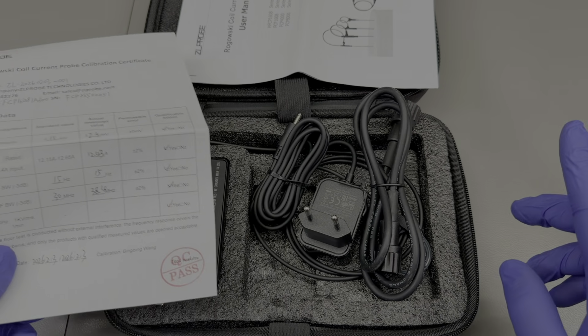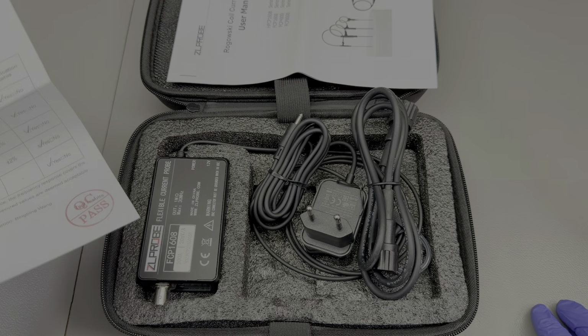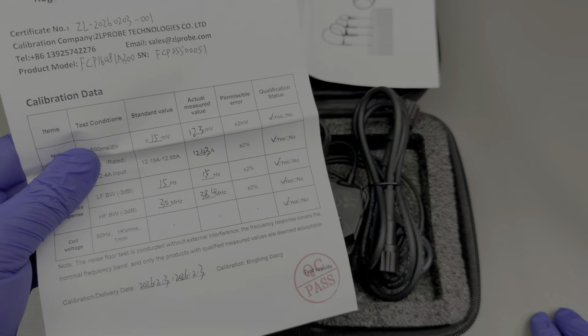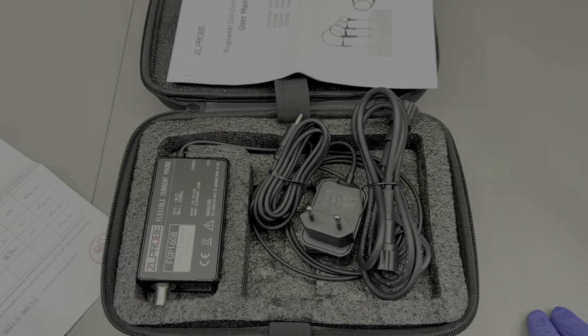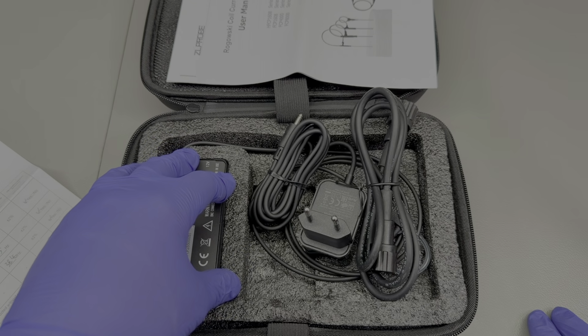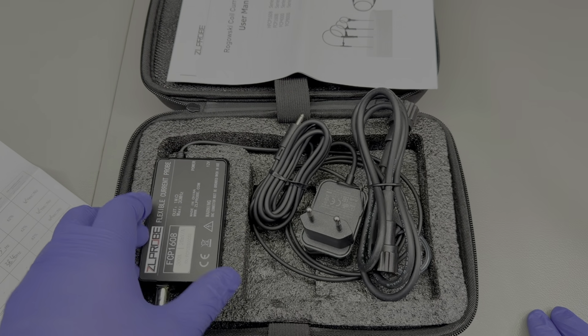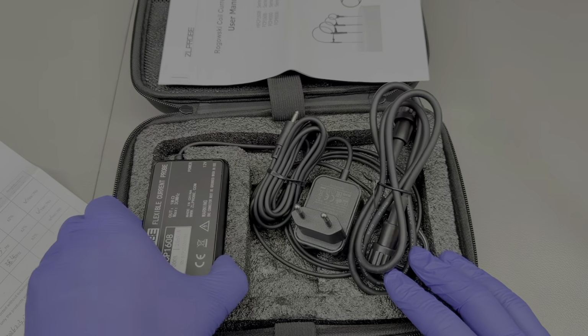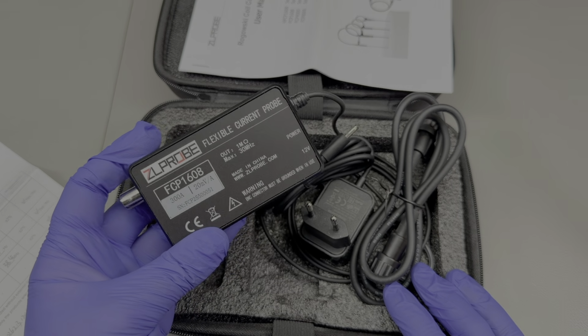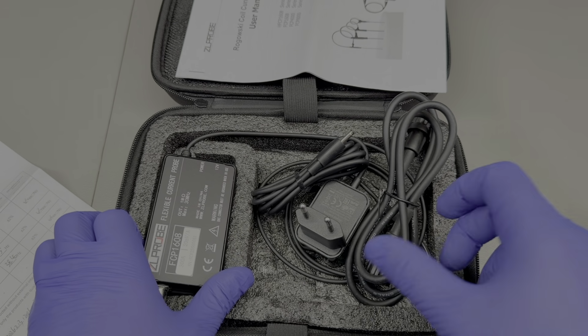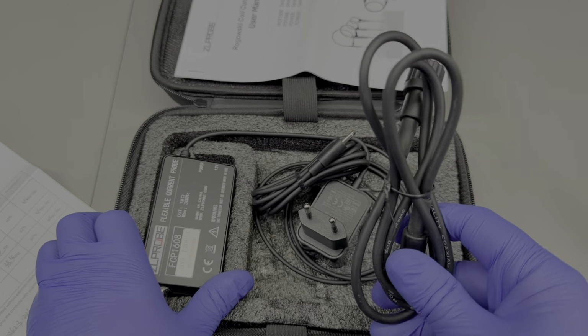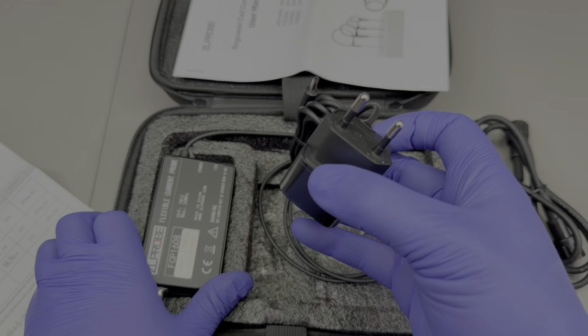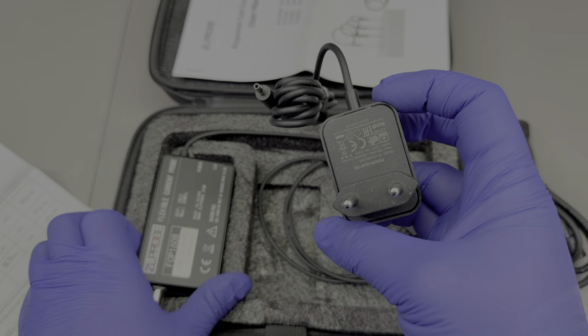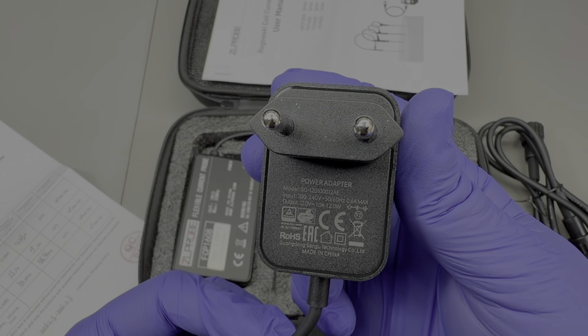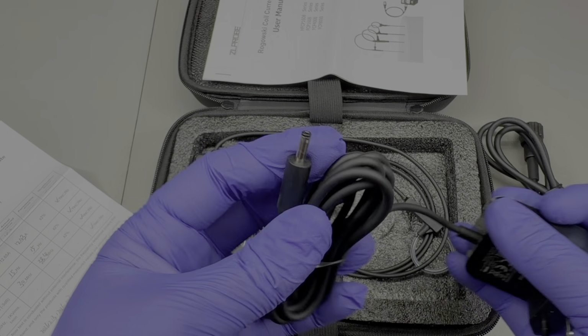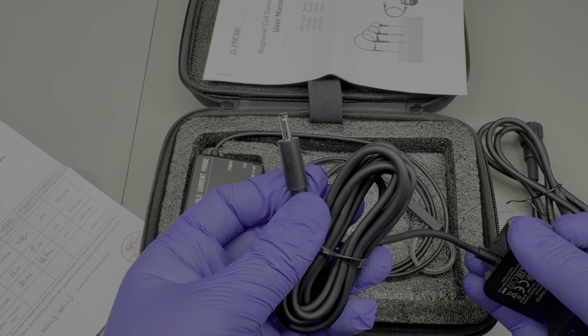The probe comes in this EVA carry case. It includes a calibration certificate. The electronics that actually amplify and integrate the signal from the Rogowski probe end are housed in this aluminum enclosure. You also get a high quality BNC cable included and the PSU required to power the electronics, which is a standard 12 volt output but uses this thin barrel jack connector.